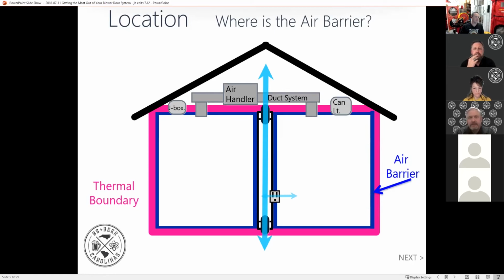But if you have no wind blowing and no fans running, you have what's called a stack effect. If you think of how a chimney works, it draws air in from the bottom and exhausts it out the top. Well, buildings work the same way, especially in the more extreme times of the year. That warm, buoyant air is going to move upward and out and draw in cooler air from the bottom. In the summer, usually that flips - as we're conditioning inside and making cooler air, it'll drop and exhale out the bottom and draw in hot attic air from the top.